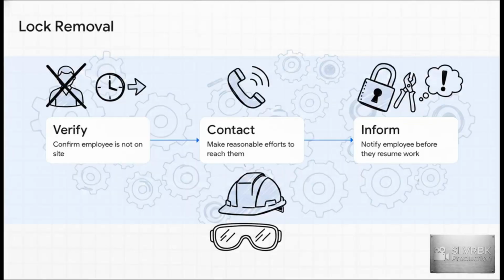Because individual control is so absolute, there is no such thing as a standard master key in LOTO. If a worker goes home and accidentally leaves their lock on a machine, the employer can't just casually snip it off to keep production moving. They have to follow a strictly documented procedure. First, verify the worker is entirely off-site. Second, make all reasonable efforts to contact them directly. And third, ensure the employee is explicitly informed that their lock was destructively removed before they ever set foot back on the floor to resume work.